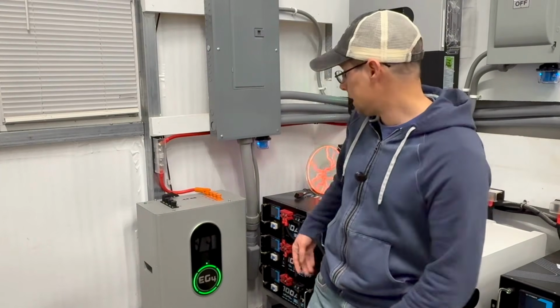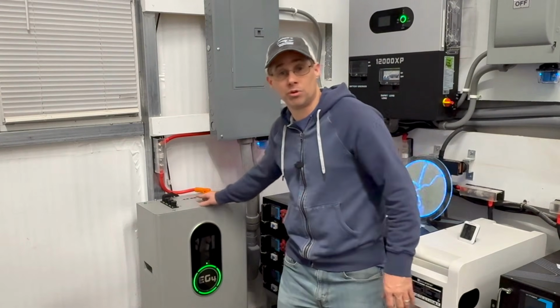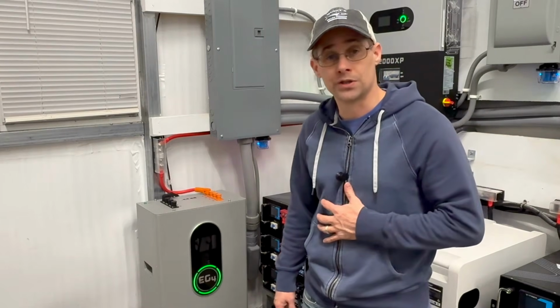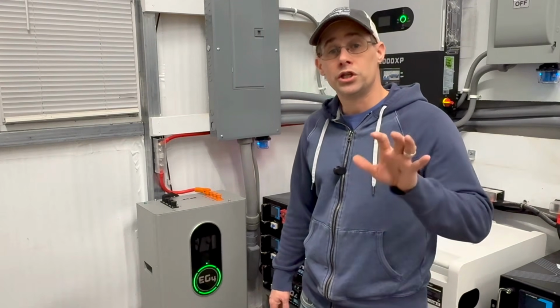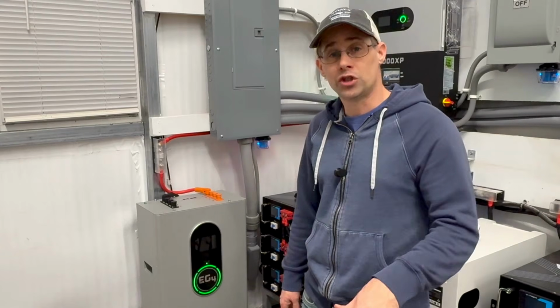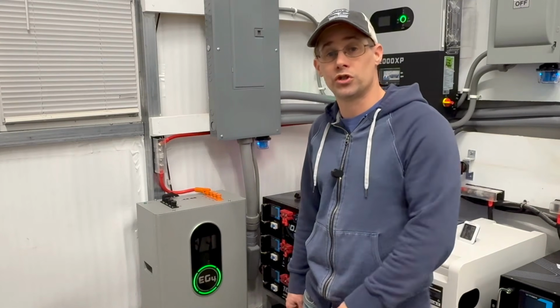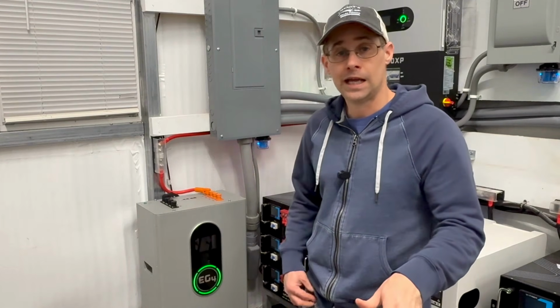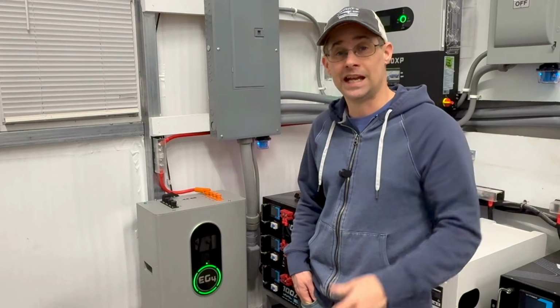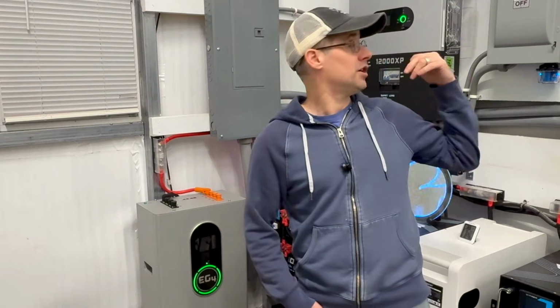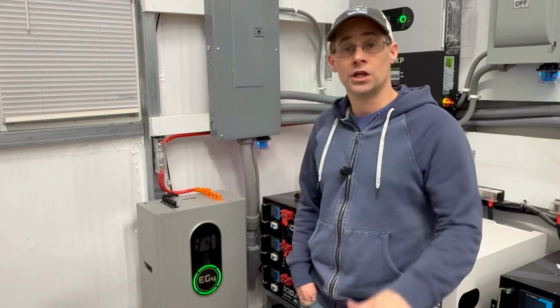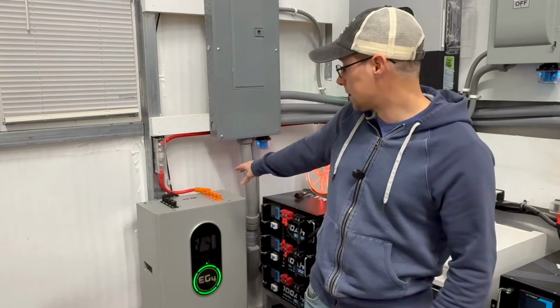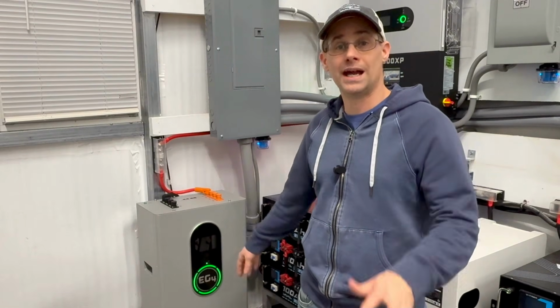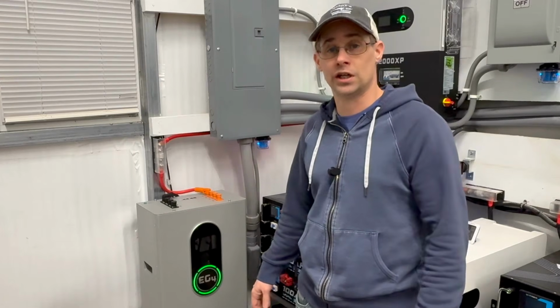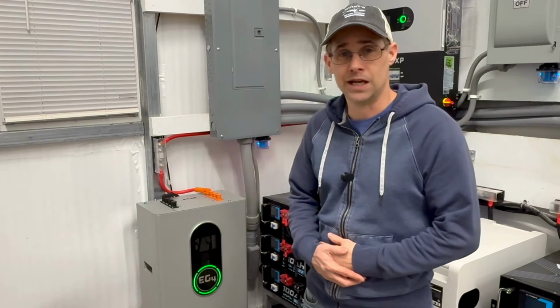As you can see, there's no communication cables connected, and that's on purpose. Little known secret: you do not need to use communications on your inverters and batteries. You can go by voltage, and that's the lead acid mode, at least with these 12,000 XP inverters. I'll go over how it's connected, why I connected it this way, why it's a very safe installation, and what my recommendations are.